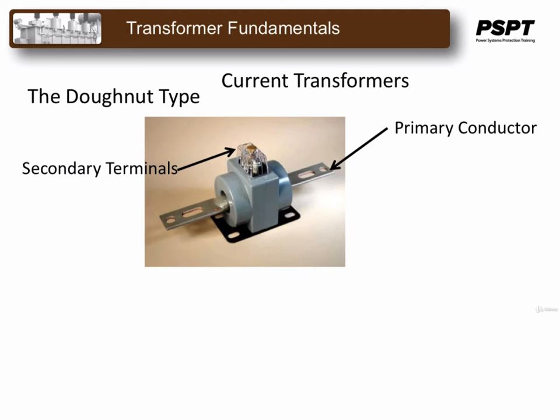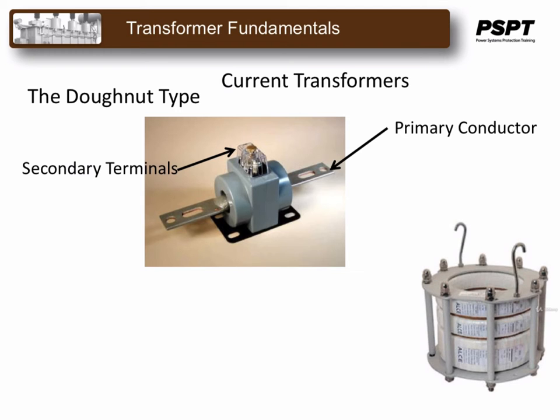If the toroid is wound with 240 secondary turns, then the ratio of the CT is 240 to 1, or 1200 to 5. The 5 amps designates the continuous rating of the secondary winding and is normally 5 amps in North America. And sometimes it's 1 amp or 0.5 amps in other parts of the world. This type of CT, or donut CT, is mostly found in circuit breakers and transformer bushings. The CT fits into the bushing turret, and the bushing fits through the center of the donut. It's not uncommon to find up to 4 CTs of this type installed around each bushing in a breaker or a transformer.